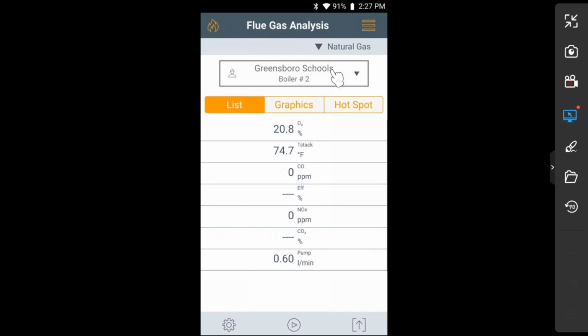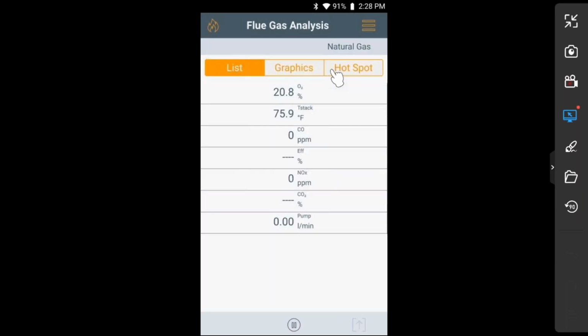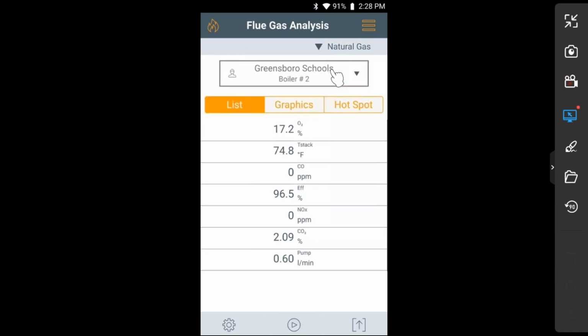And what I can do now is, when I'm taking a test and I start the pump and I start getting my readings of flue gases, you see what I'm doing is I'm driving down the oxygen reading a little bit. I'm going to stop the pump. This is not your typical reading in a boiler, but I'm simulating this here in my office. But you've got the percent of oxygen on top. You've got the stack temperature. Percent oxygen should be anywhere between 4 and 6 or 7% oxygen, depending on what type of combustion process you're on. Stack temperatures could be in the 400 degree range.